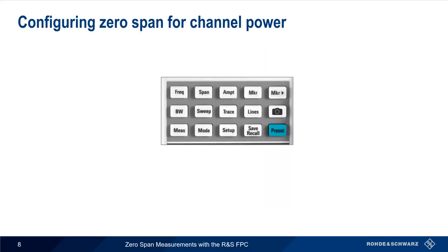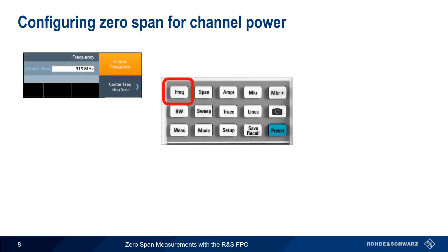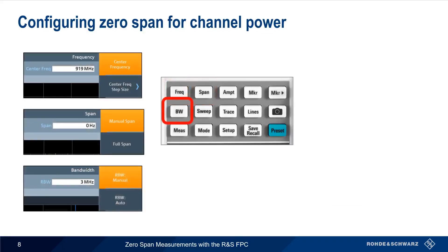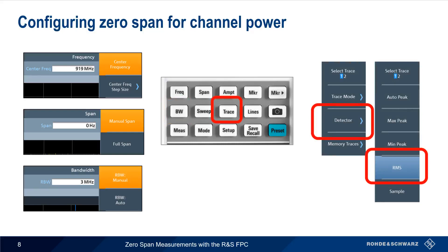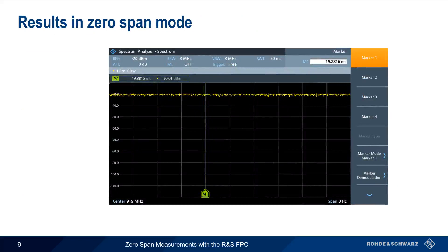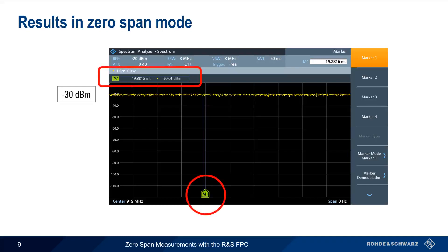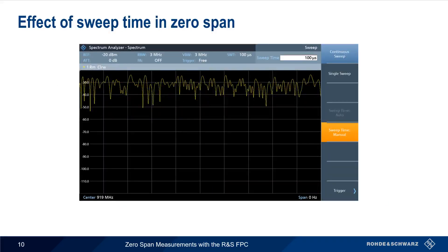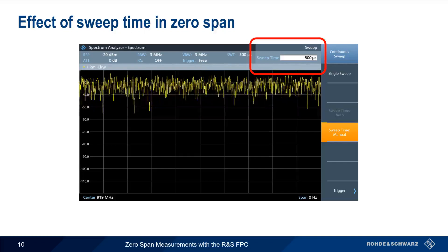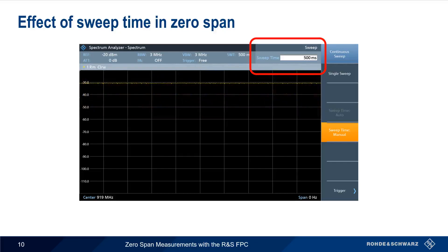Now let's look at measuring channel power using zero-span. As before, we set the center frequency, set span equal to zero, and then choose our resolution bandwidth. Because we're making a power measurement, we also need to set our detector type to RMS, since this is the proper detector to use when measuring power. Assuming that the power of the channel is relatively constant, channel power should appear as a more or less horizontal line on the power versus time display. We can either read the value from the vertical axis, or use a marker to obtain a more precise value. One important parameter when using zero-span to measure channel power is sweep time. Generally speaking, increasing the sweep time will improve the stability and repeatability of our measurement results.